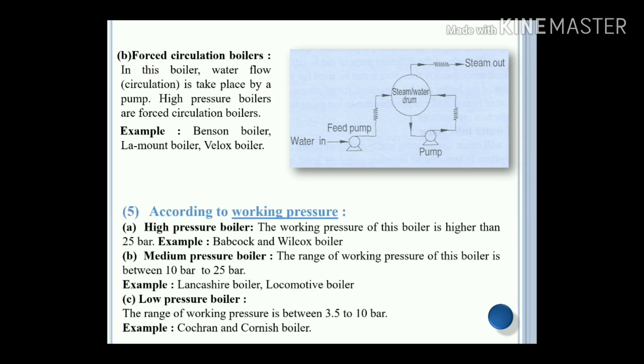According to the working pressure — this is a key criteria for selection of the boiler in engineering applications. High pressure boiler: the working pressure is higher than 25 bar. Example: Babcock and Wilcox boiler. Medium pressure boiler: the working pressure ranges between 10 bar to 25 bar. Example: Lancashire boiler and locomotive boiler. Low pressure boiler: the working pressure ranges between 3.5 bar to 10 bar. Examples: Cochran boiler and Cornish boiler.